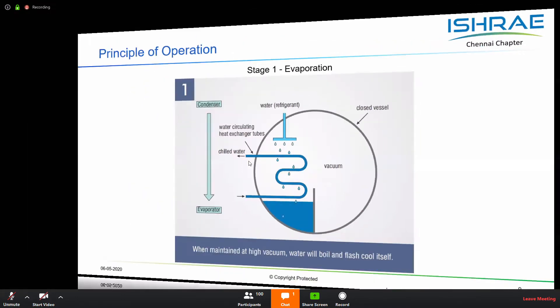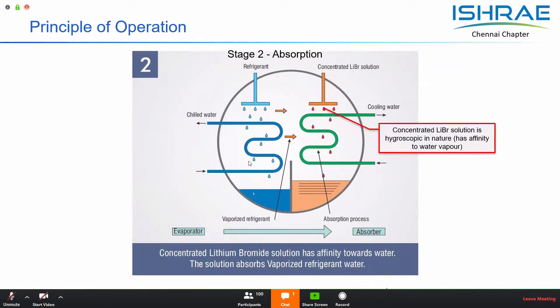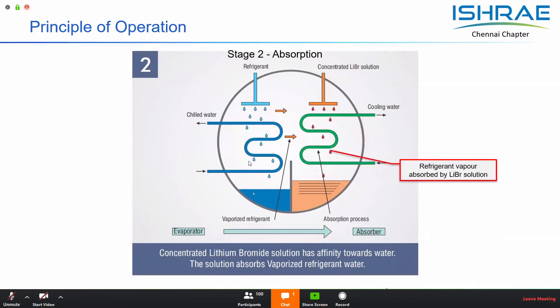The role of the absorber in this absorption system is to maintain the vacuum inside the machine by absorbing the refrigerant vapor coming from the evaporator. We spray a concentrated solution of lithium bromide in the absorber chamber. This lithium bromide solution at higher concentration is hygroscopic, meaning it has an affinity towards water vapor. When this water vapor is absorbed, the heat of dilution is released to the lithium bromide solution, which heats it up.